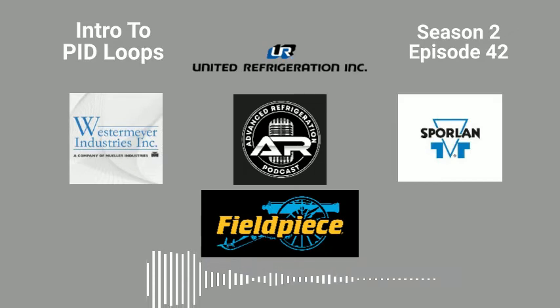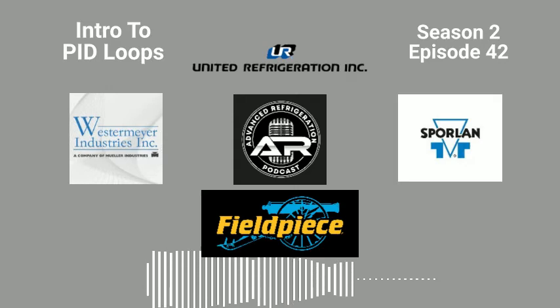No. I wanted to go over, first of all, that everybody's PID tuning is different, whether it be Micro Thermo, CPC, Danfoss, RDM. Everybody's is different. Some of them are reverse, some of them are forward. Some of them, when you increase values, it makes it slower. Some of them, when you decrease values, it makes them faster. So just for you guys to be aware before we go into all this, we're going to go over general PID stuff, but everybody's PID is different. Don't just take this to heart and think it's going to be the gospel for every single unit. Every single company has their own way of doing PIDs, so everyone's going to be a little bit different. Some of them, no two are going to be the same.